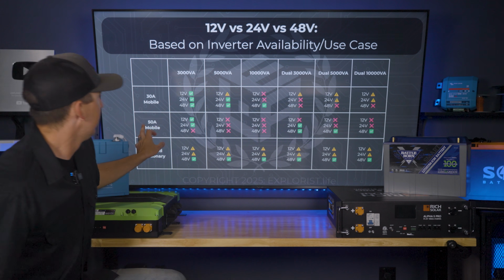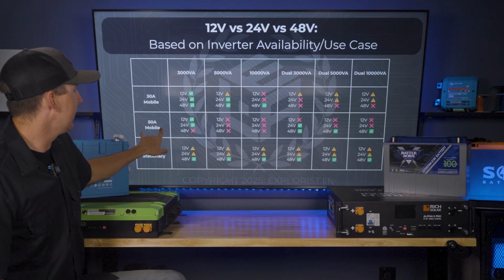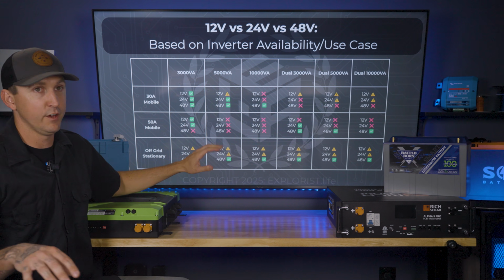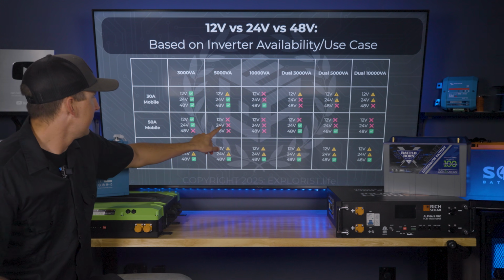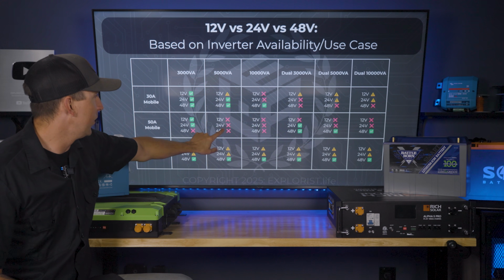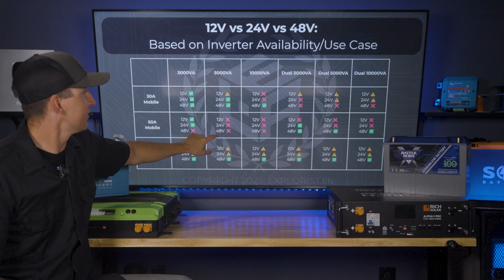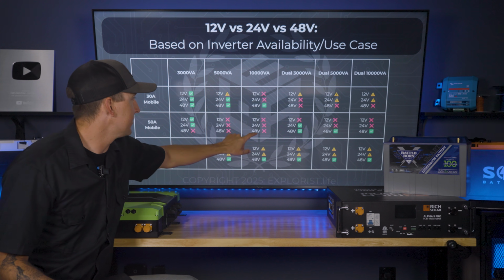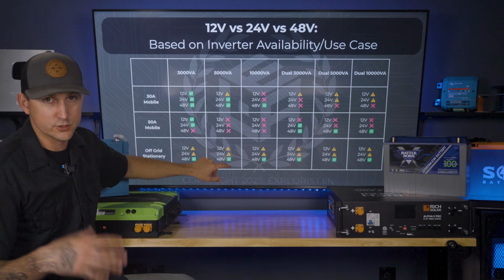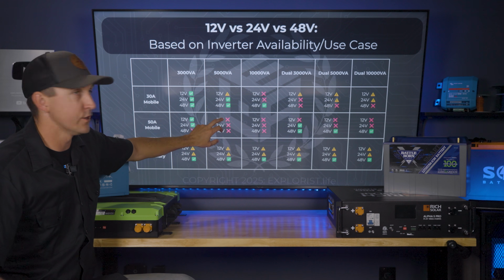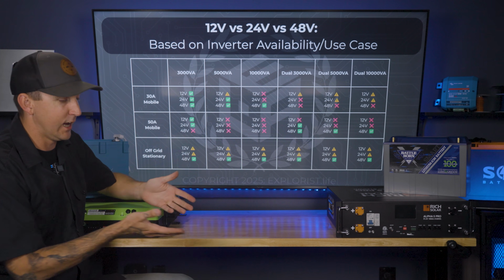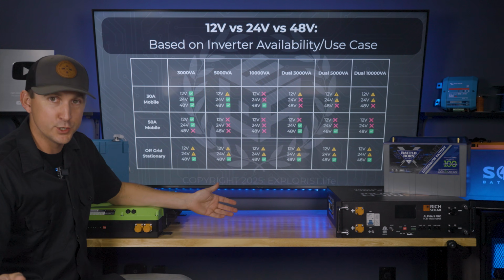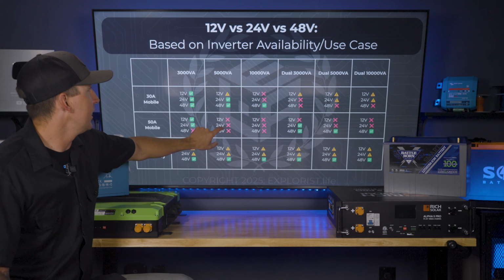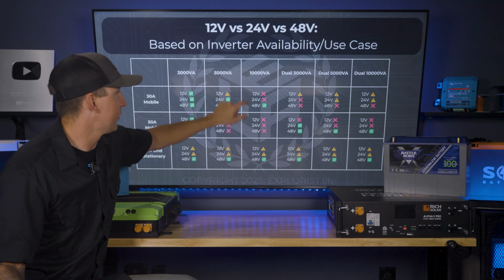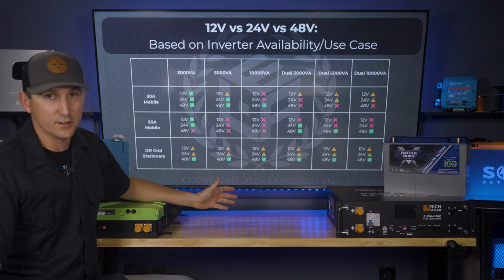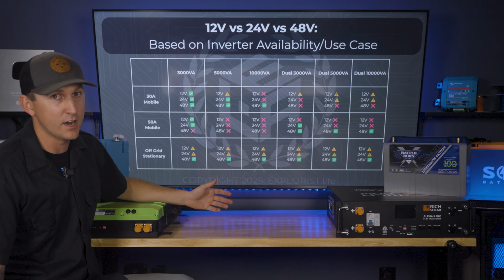We're limited by actual inverter availability, because you'll notice for that 5 kVA, we don't have any options - we've got X's across the board here as well as here. That's because, with Victron at least, they don't make an inverter charger that has enough wire slots for 120/240 input for either of these sizes of inverters. So as of shooting this video, that's just simply not an option.